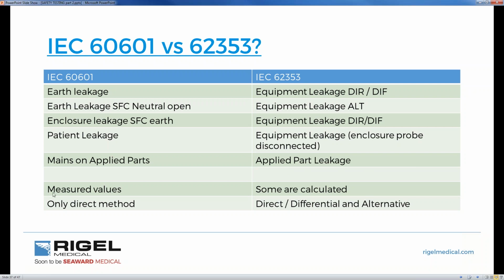The 60601 is all using the 1K body model. Some of the 62353 tests use scaled and factored calculations to get the correct measured leakage. The 60601 uses the direct method only. 62353 has 3 different types of ascertaining and measuring hazardous currents.